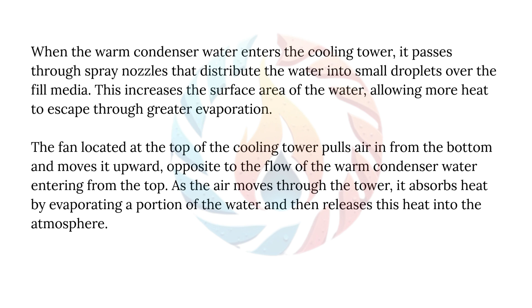The fan located at the top of the cooling tower pulls air in from the bottom and moves it upward, opposite to the flow of the warm condenser water entering from the top. As the air moves through the tower, it absorbs heat by evaporating a portion of the water and then releases this heat into the atmosphere.